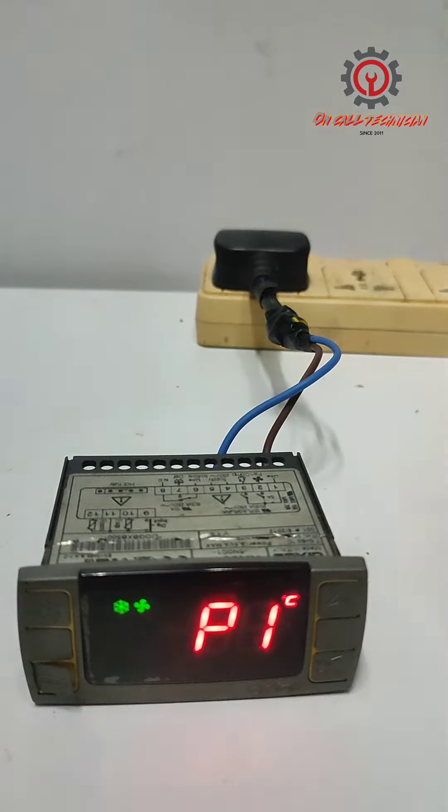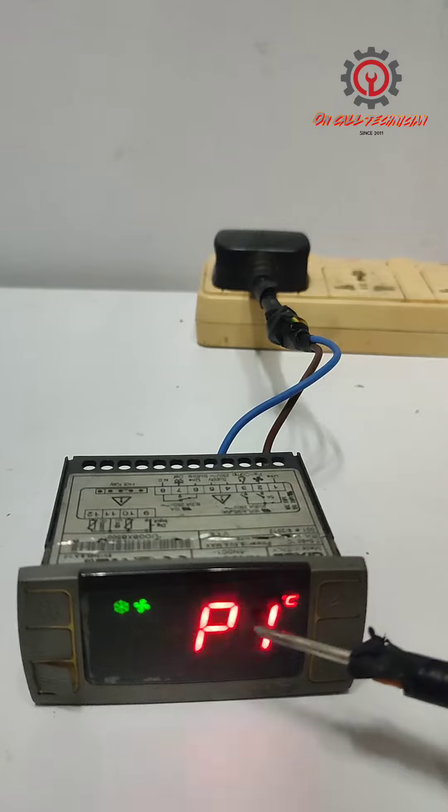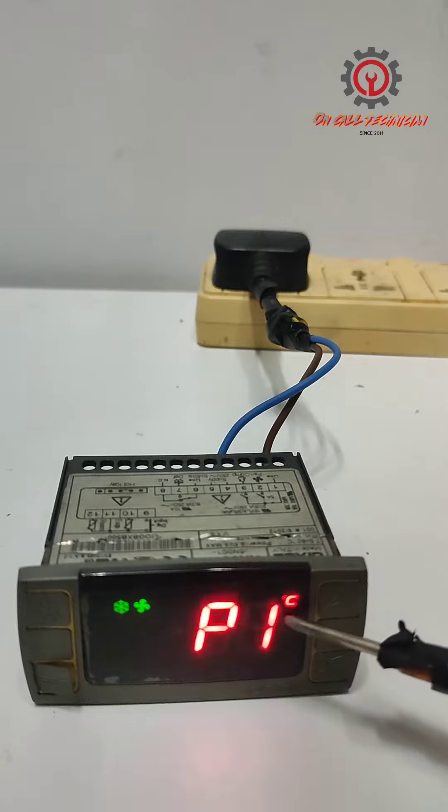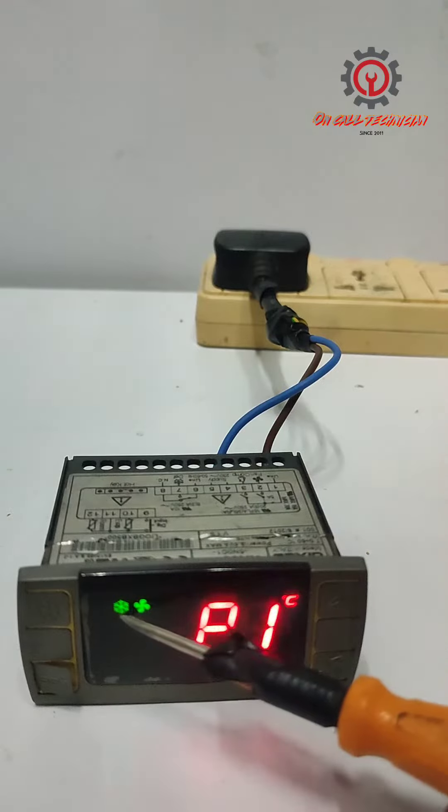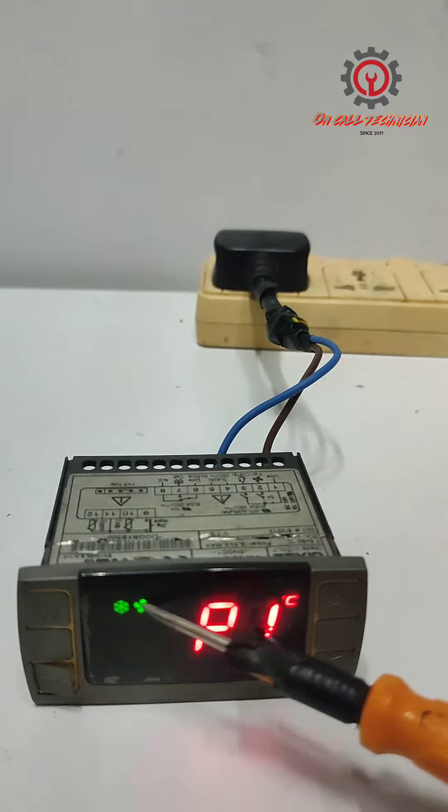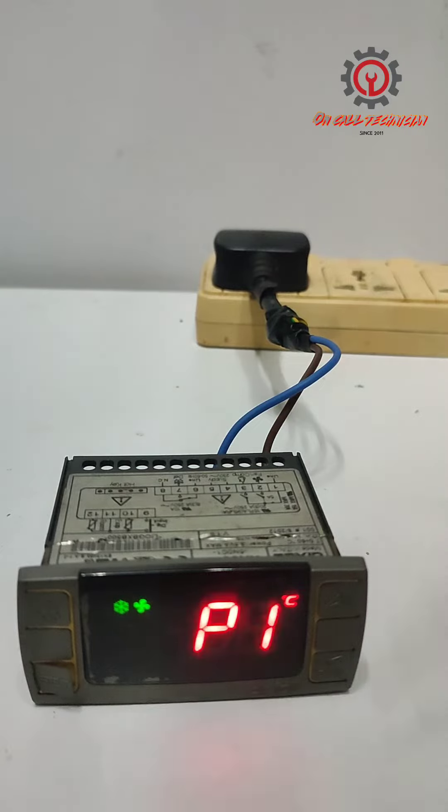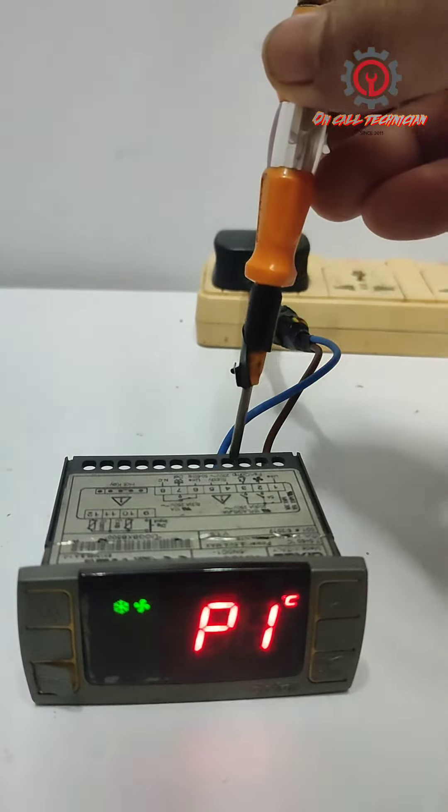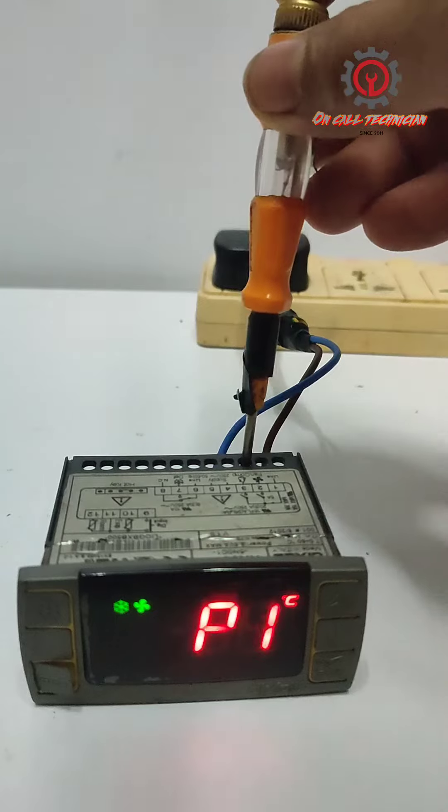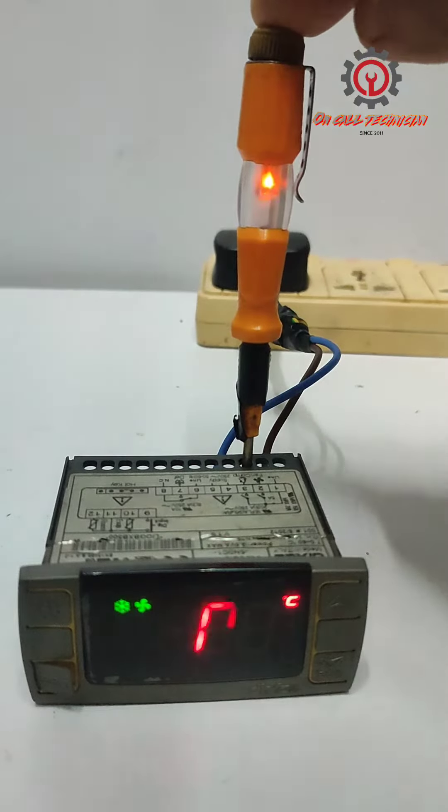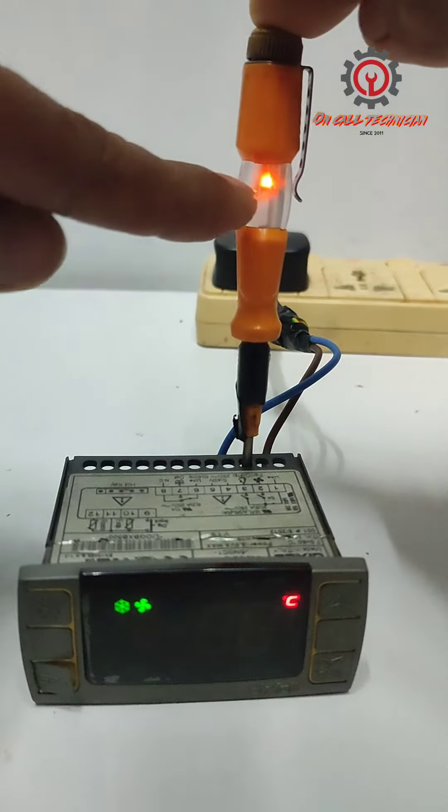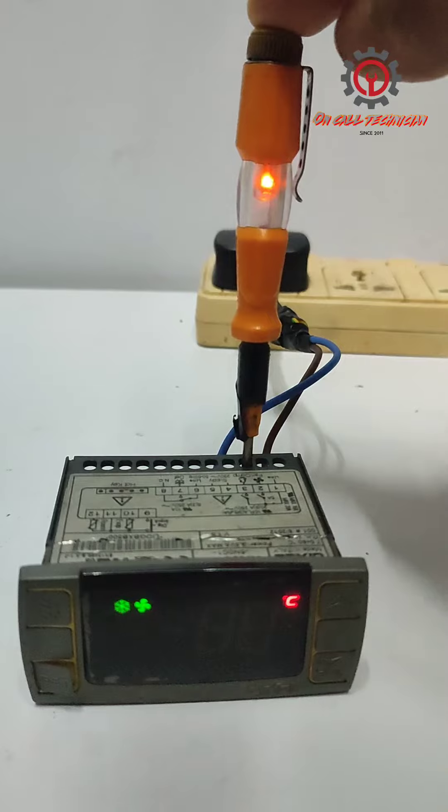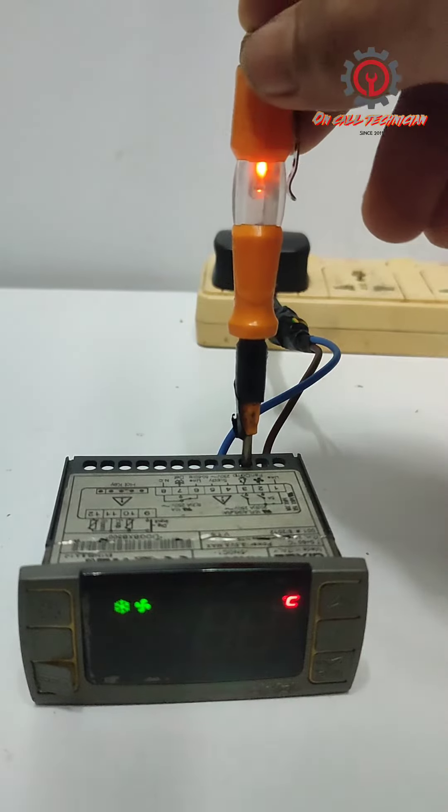Okay, P1 appears, but the compressor symbol and fan motor are active. Terminal number three is for the line compressor. Take a look, my test pen lights up, meaning the output relay sends signal.